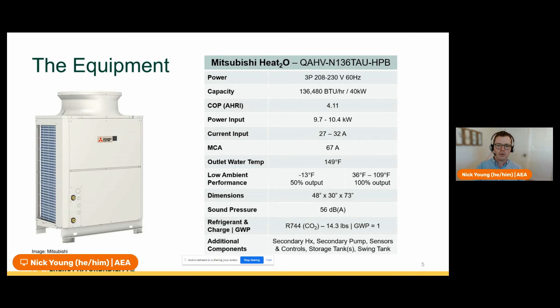This is the Mitsubishi Heat2O. I've got the model number. It uses three-phase 208/230 power. It has a capacity of 136,480 BTUs per hour, or about 40 kW of output, and an AHRI rated COP of 4.11. You can see the power input. I'm not going to read through all of these, but this gives you a basic idea of the parameters for this piece of equipment, and crucially the dimensions. It's about 4 feet wide, about 2.5 feet deep, and a little over 6 feet tall, so it's about the size of a VRF outdoor unit. There are some additional components, and we'll talk about what those are and what you need to keep in mind for them.